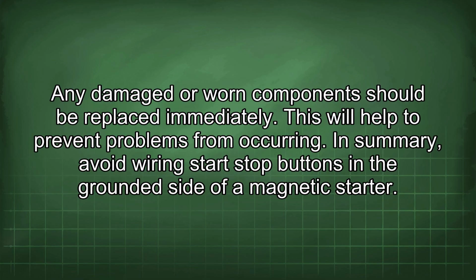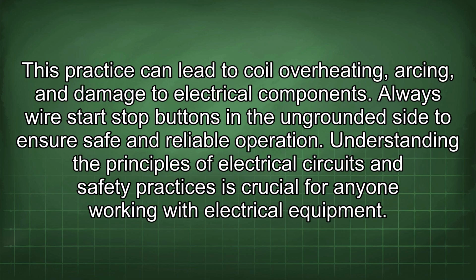In summary, avoid wiring start-stop buttons in the grounded side of a magnetic starter. This practice can lead to coil overheating, arcing, and damage to electrical components. Always wire start-stop buttons in the ungrounded side to ensure safe and reliable operation.